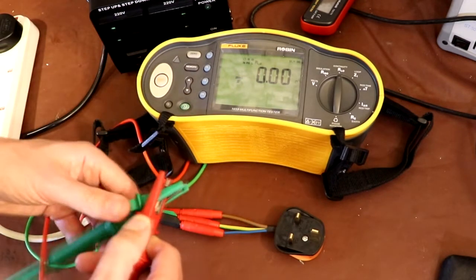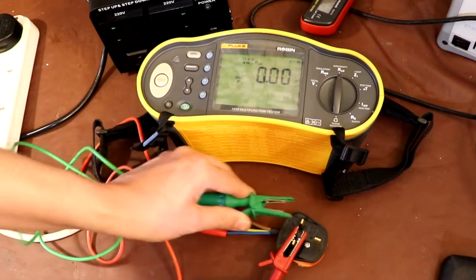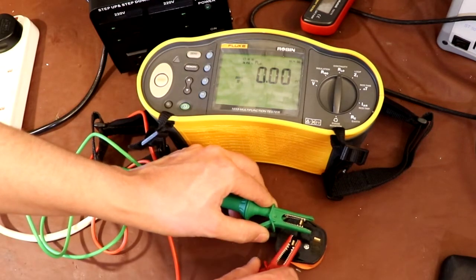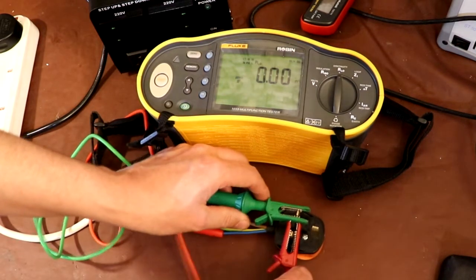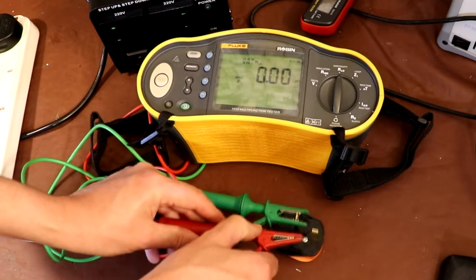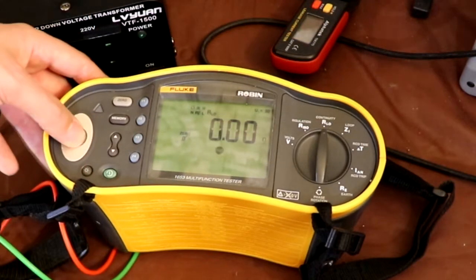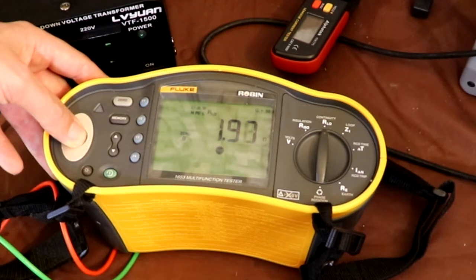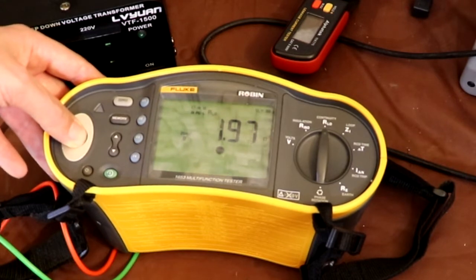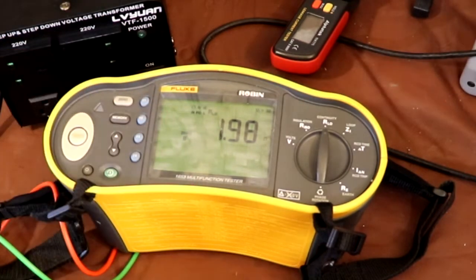So I get the leads now, I'm going to clip them across there. I'm going to make sure we've got a good connection, and we just measure the resistance, press test again. So the resistance of our transformer primary and the connecting wires is coming up there as 1.98 ohms.